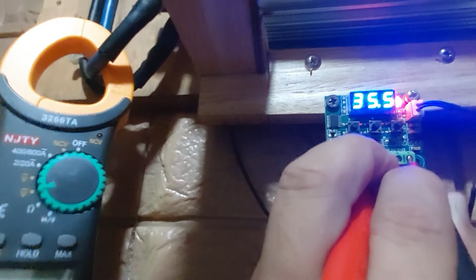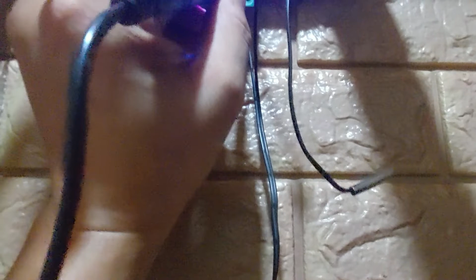Okay, so let's remove the sensor, just leave it hanging, and wait for the trigger to turn off. If the temperature drops 2 degrees below the set value, it will turn off the relay. Just wait for it. It should turn off at 33 degrees. Okay, so the relay is now off. So the voltage here with respect to ground should be 0 or negative. Okay, so let's try to hook up the Arctic air and test it again.